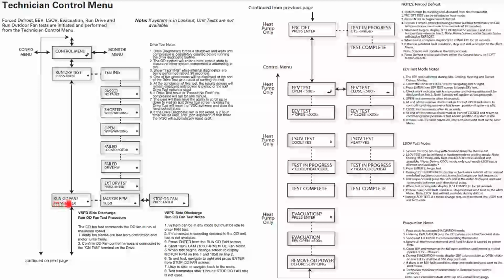We can run outdoor fan test if we have some kind of high current, possibly not defrosting correctly and ice buildup, or if we have a bush in the way or overgrown vegetation blocking the coil, or a bunch of cottonwoods on the coil. We can run that outdoor fan test, and it ramps all the way up to its maximum RPM. So if we do have an issue with the outdoor fan motor, we have a test we can do. We can do a forced defrost. We can also do this from the thermostat while in test mode, or with the button on the drive itself.